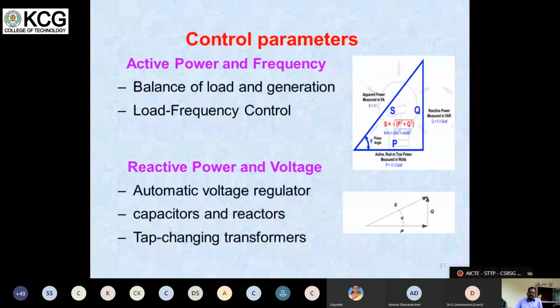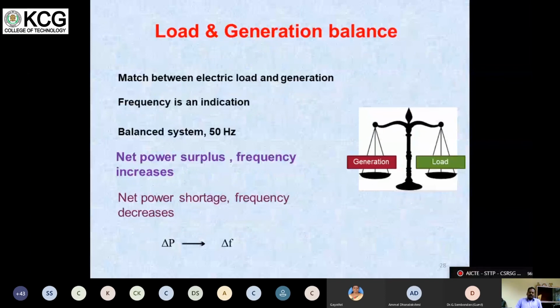So these are the control parameters: active power and reactive power. Active power controls frequency, reactive power controls the voltage. So we have to manage and balance this load and generation. Load and generation should be balanced. Then only will we have constant frequency and constant prescribed voltage in the grid system. With a net power surplus, frequency increases; with a net power shortage, frequency decreases. So the frequency depends on the active power.